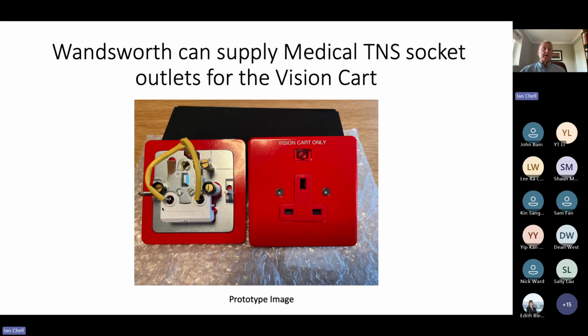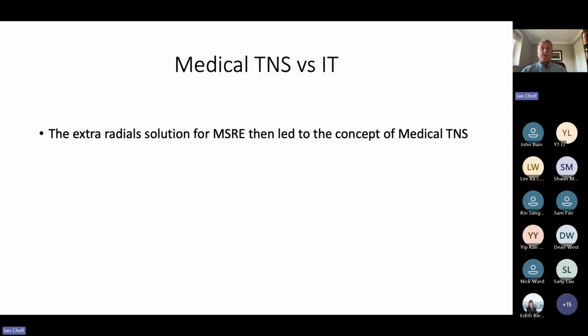So this then led to the bespoke sockets that Wandsworth can supply. They did me a great favour by making these prototypes. I can only suggest that you go to them. Now, if you notice, the supplementary earthing and extraneous are separate because it's on spacers. So the supplementary equipotential bonding protective earth is wired exactly the same as medical IT sockets. So all of this led to the concept for medical TNS.